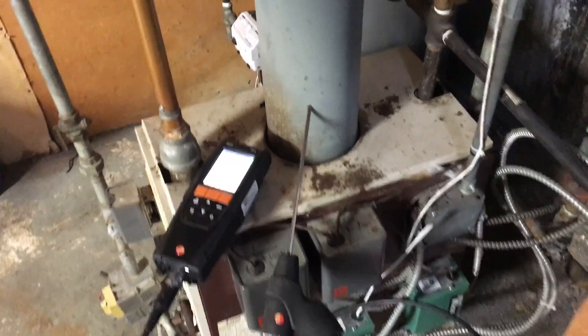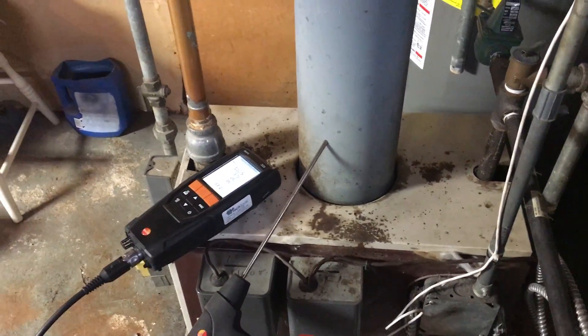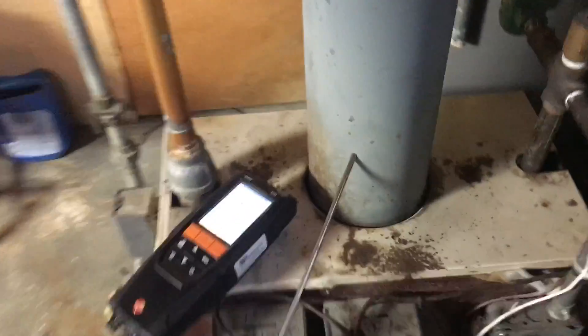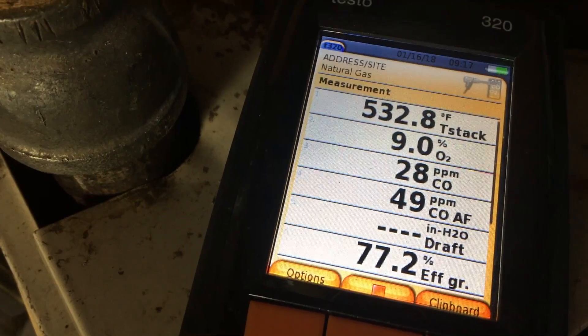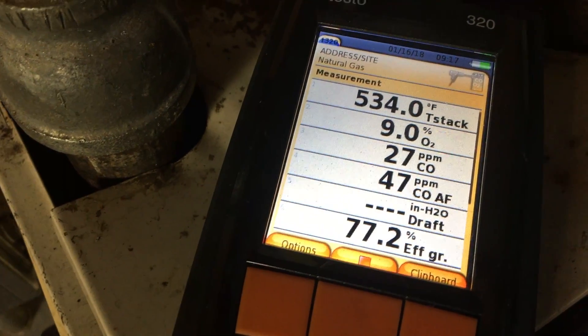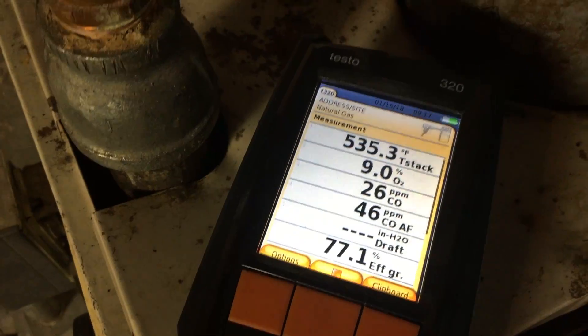Follow-up video: with the help of the homeowner, we scrubbed the cast iron sections clean and put everything back together. We're doing a combustion analysis now. I did have to crank down the gas valve a little to lower the pressure and bring down the carbon monoxide, which was almost 300 particles per million. Now we're at 27 ppm and holding.